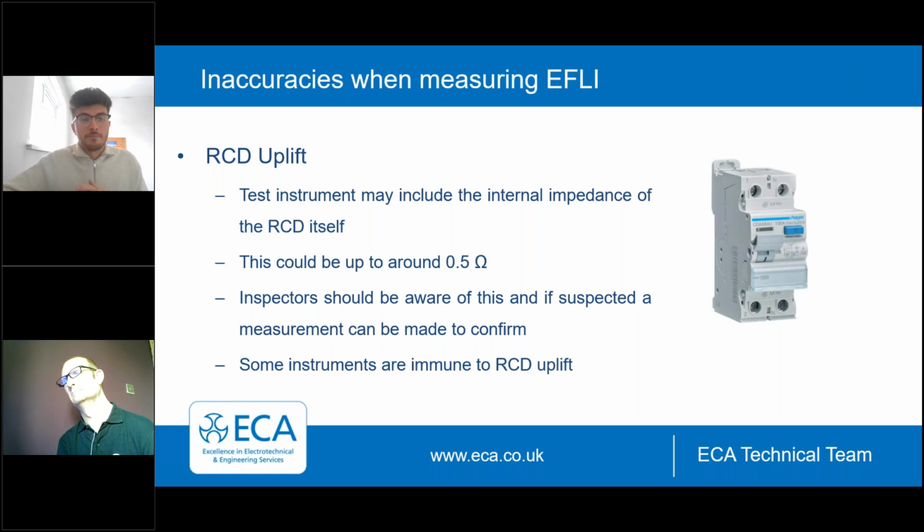Now, of course, that may give you issues when you look to verify your result. It may be a lot higher than you expect, and then you may be questioning that you potentially have a fault or an issue on your circuit. So this is something that inspectors need to be aware of.